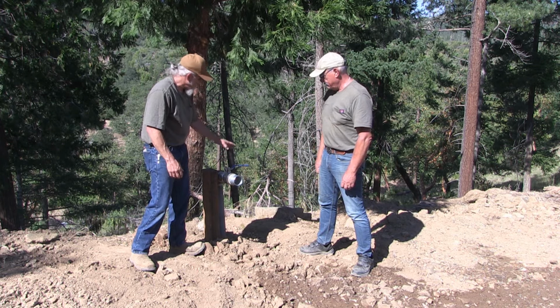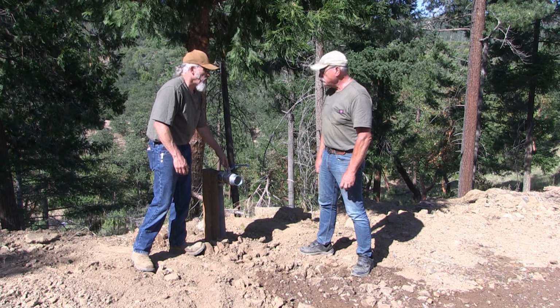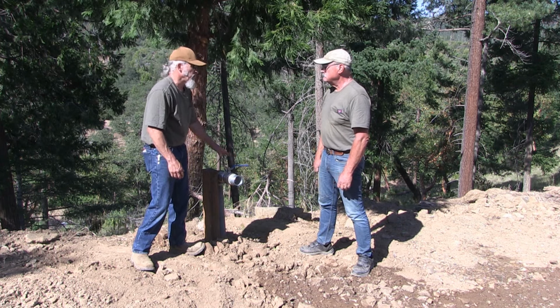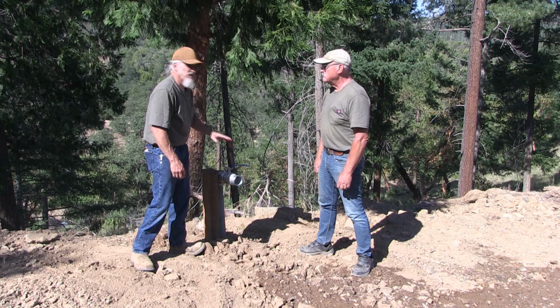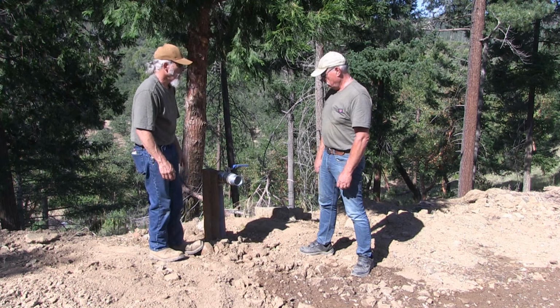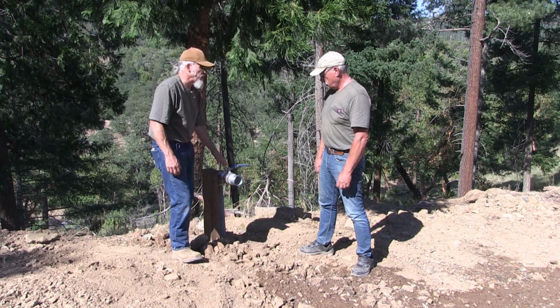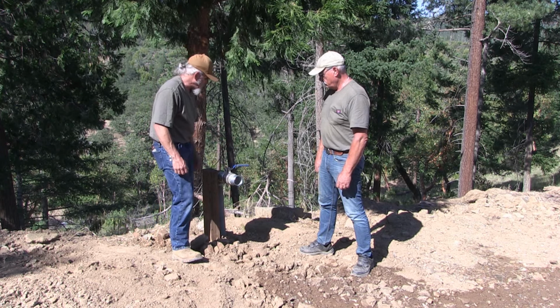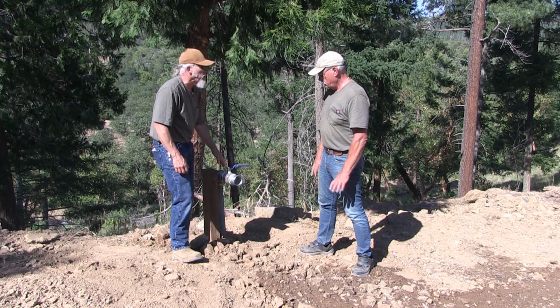Even the 3-inch was difficult, but you have to have at least 3-inch for any fire department or any fire apparatus that would come. They won't pull off anything that's less than 3-inch. So if you had a 2 or 2.5-inch, they won't even bother with it. Good to know. So you need the volume and all that the 3-inch gives. So 3-inch minimum, 4-inch is obviously better. Yeah, obviously more volume, more pressure, but this is the best we can do on our budget.